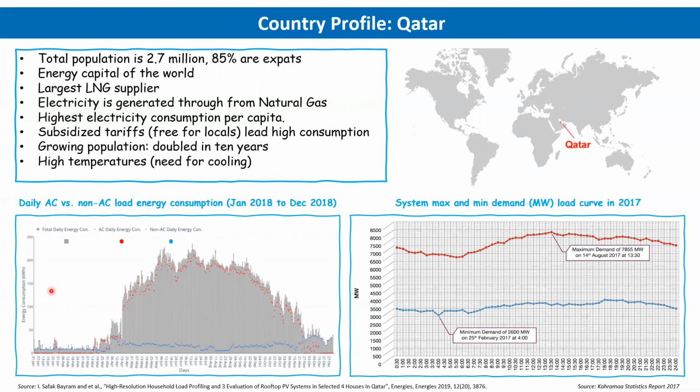To sum up, peak load is a key system parameter in Qatar because of the AC load, especially during the summer. It determines how much generating capacity will be needed and when demand is highest. Even though peak loads tend to align with specific seasons, electric systems must be able to deliver the maximum load at all times. It must. As I mentioned before, a fleet of electric vehicles may increase peak loads if charging aligns with maximum demand for other users. Since we have the highest demand here, if we charge our EV fleets at the same time, it will create problems from the grid perspective.